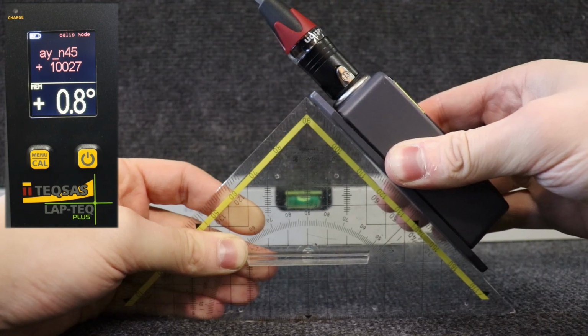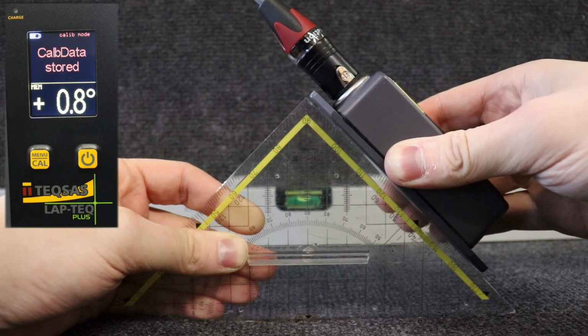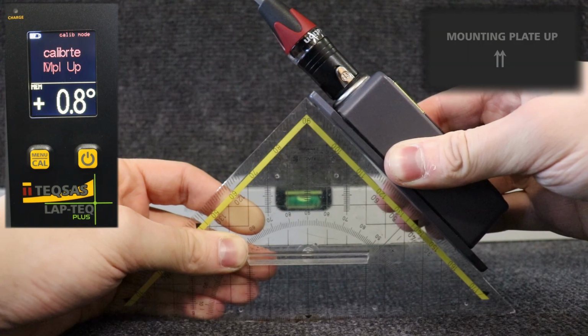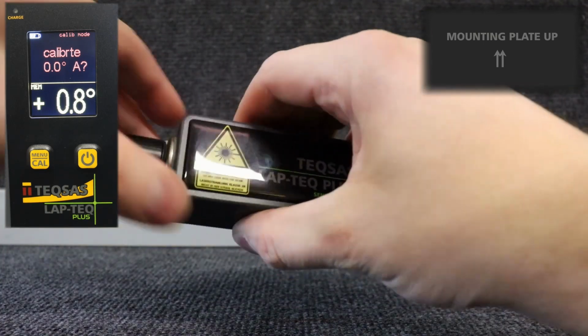After a little while, the display shows calibration data stored. The calibration has been completed for this mounting position with the mounting plate facing up. We could stop now and power off. However, if we want to use the sensor in a different mounting position, we have to keep going.